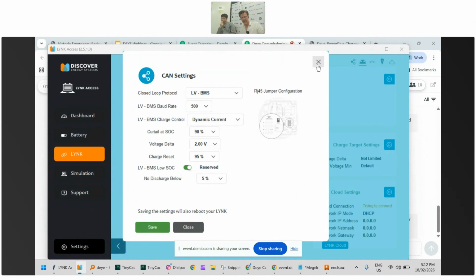I haven't seen any of them have got worryingly over voltage, but sometimes the BMSs are quite trigger happy, and they basically see any voltage that is above what they've asked for as a potential problem, so they'll switch off, even though they're well below the danger area. They'll switch off.